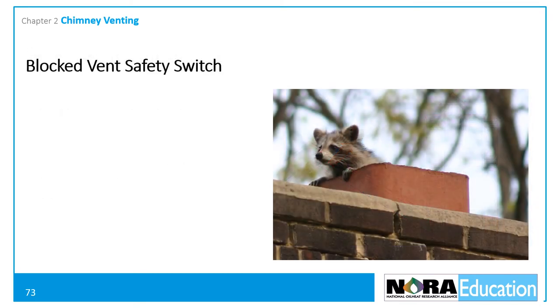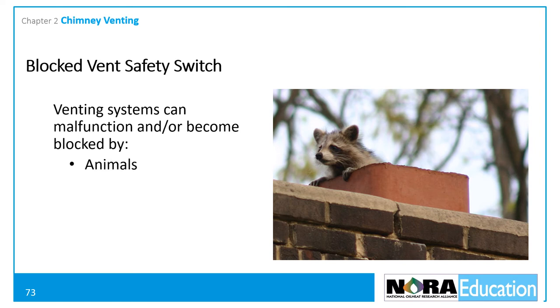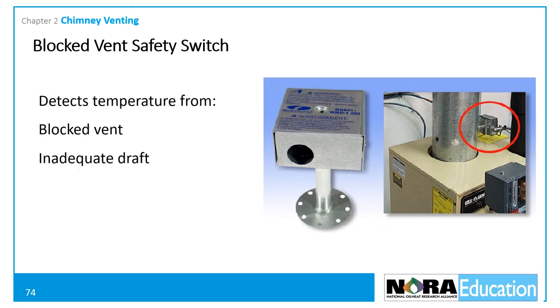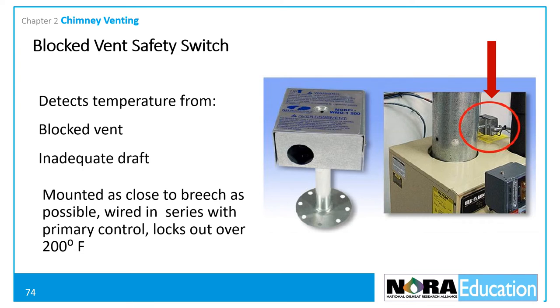This section addresses blocked vent safety switches. Venting systems can malfunction or become blocked — animals sometimes enter the system, soot can accumulate, and chimney liners can deteriorate. When the vent system malfunctions, flue gases including carbon monoxide can enter the building. Thermal safety switches detect a temperature rise above a set point caused by a blocked vent, indicating inadequate draft. These manual devices lock out when they sense a temperature above 200 degrees Fahrenheit. They are mounted as close to the appliance breach as possible and wired in series with the primary control to prevent burner operation when there is a blocked vent.